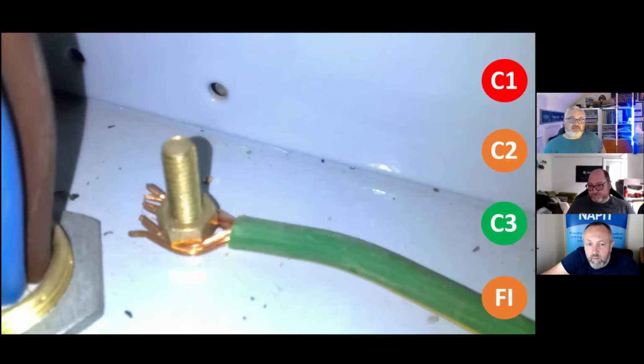So this, to me, is one of the few earthing codes that I actually do C3 on, because on a lot of earthing systems, if it's dealing with a protective bonding conductor, an earthing conductor, or a CPC, I'll look at C2 as a default solution. But this one here, due to the fact that most of your earthing is actually going via that gland and that brass nut, which is going into the panel...